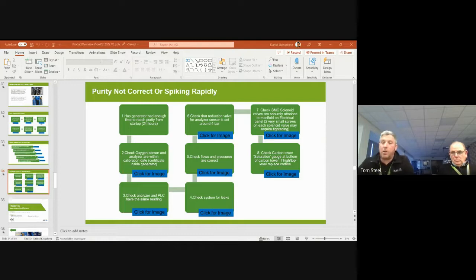They don't have a lifespan as such. We have years and years of experience with no issues. The biggest issue you find is if you saturate it with oil or with too much moisture, and that can cause issues. That's normally associated with everything associated with the generator itself. The generator is very robust. As long as it's maintained, it's very efficient, and it works very well. But if the compressor side is not maintained correctly, or if the filtration is not replaced periodically, then that's where you'll start to see the issues. But if you maintain everything associated with the generator as well as the generator itself, then you shouldn't see any issues with the zeolite compound at all.